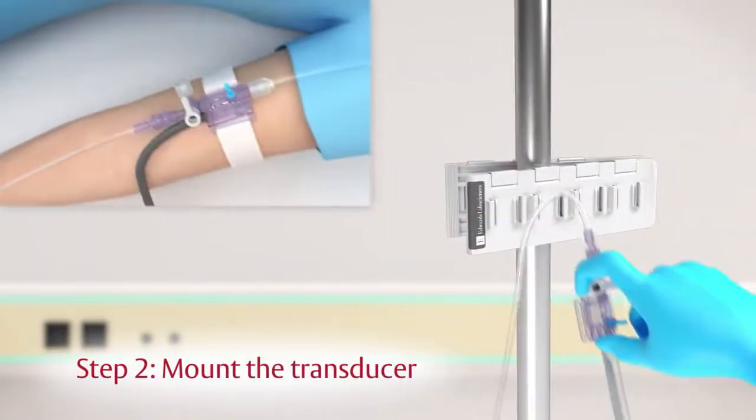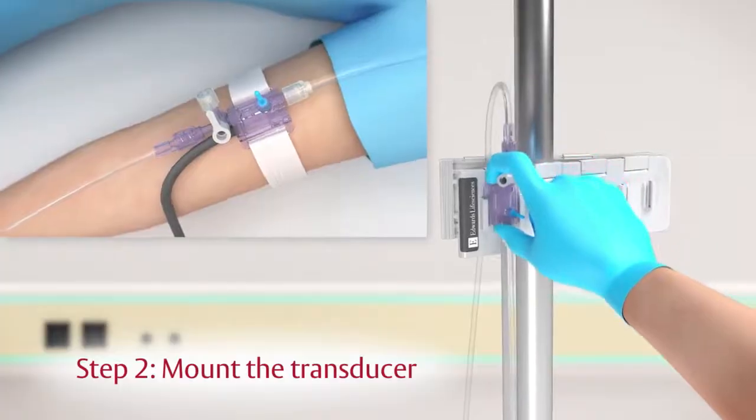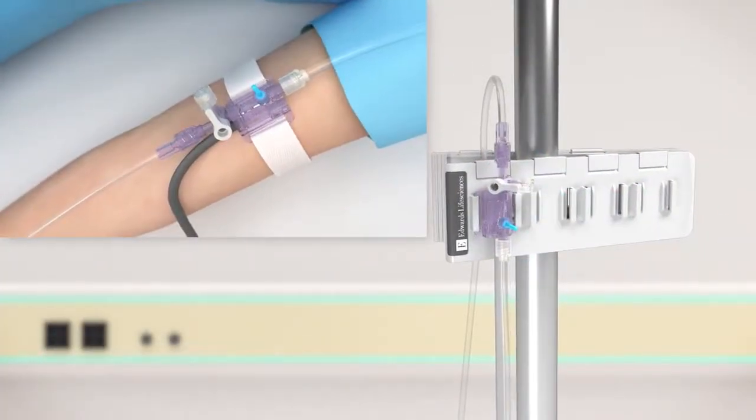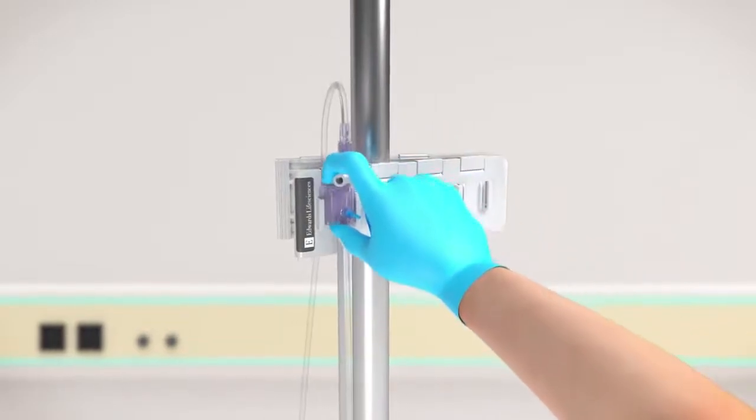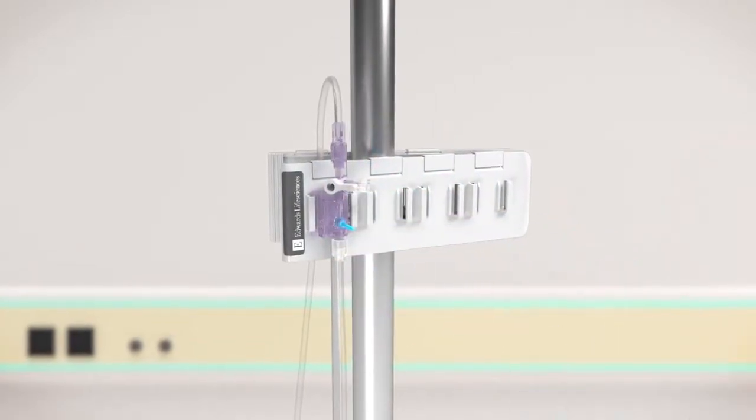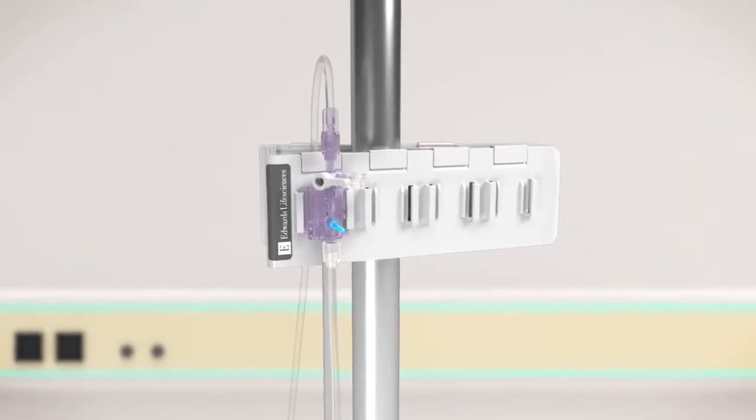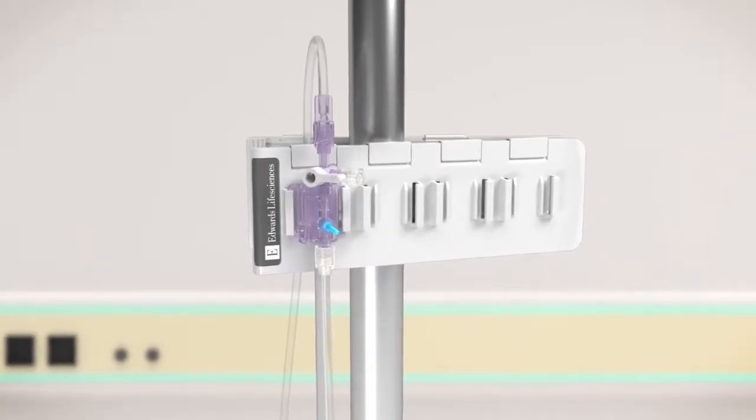Step 2: TruWave transducers can be mounted on either an IV pole or on the patient's arm. The setup procedure is the same. This video demonstrates the pole mounted method. Insert the TruWave transducer into a mounting backplate that is secured on an IV pole.